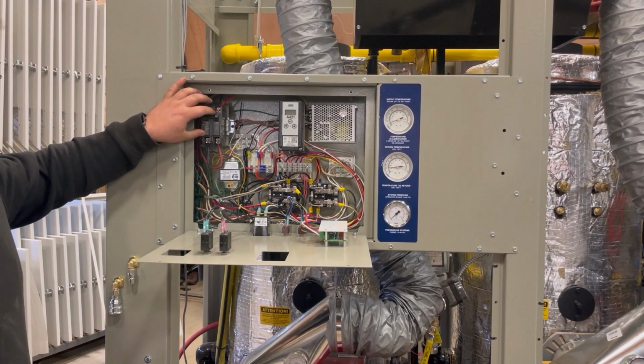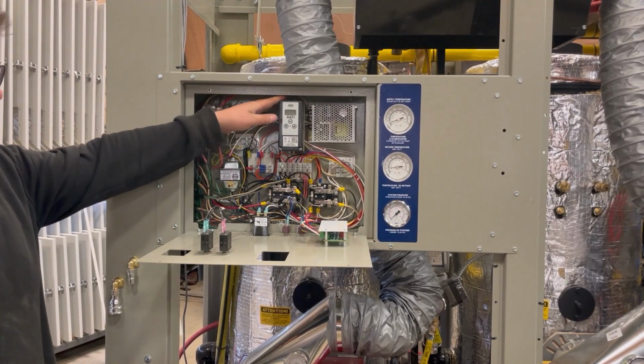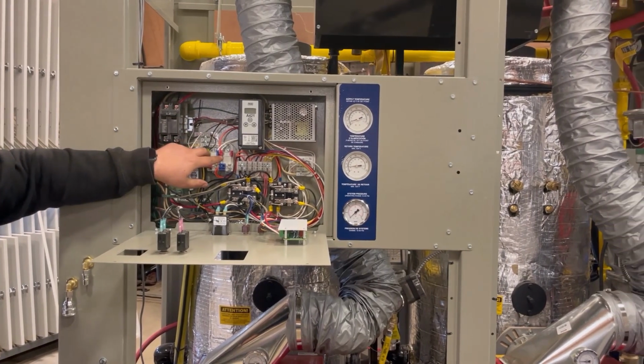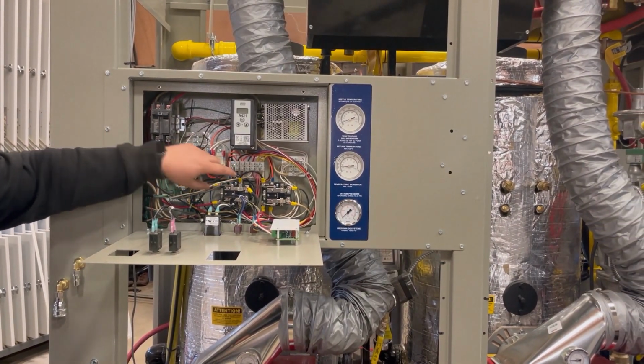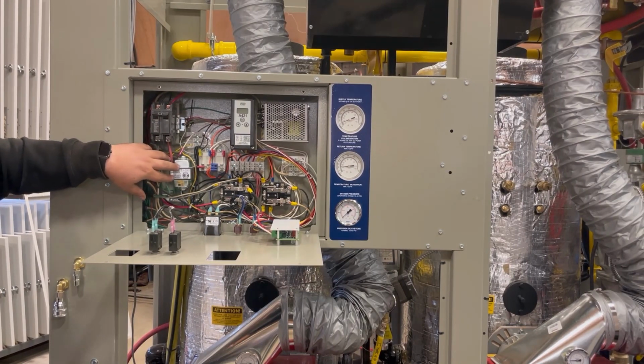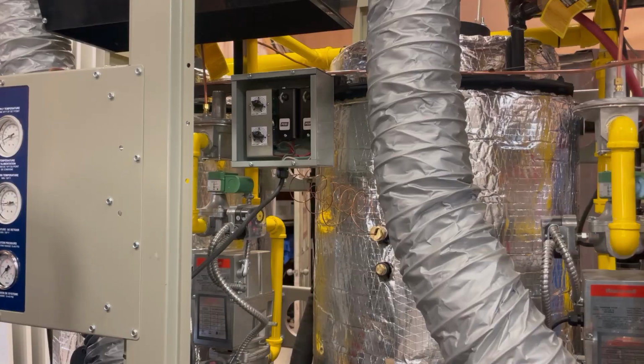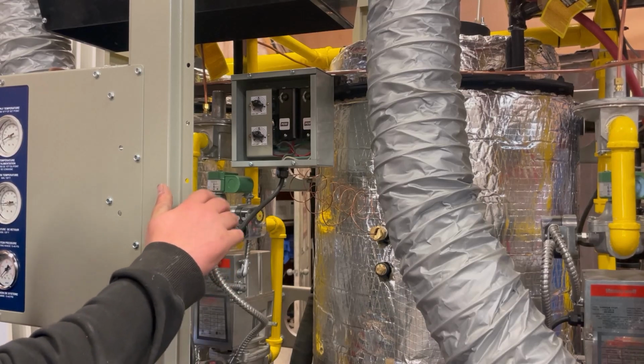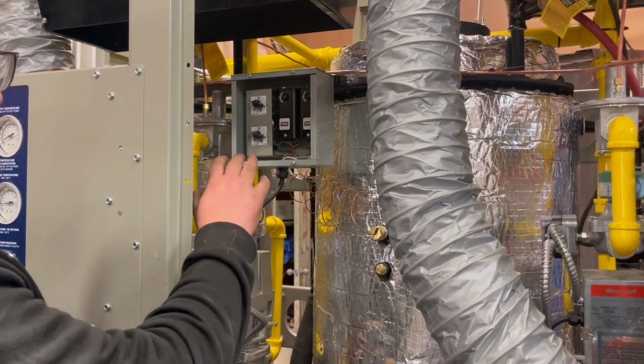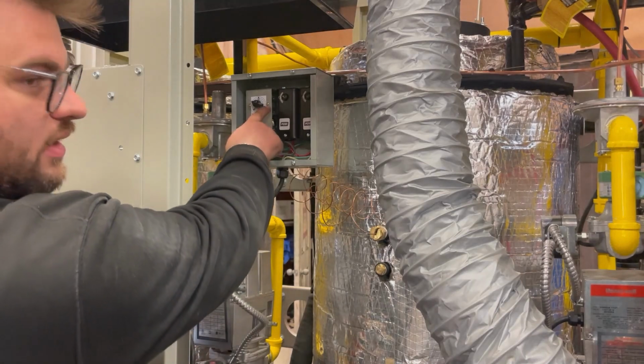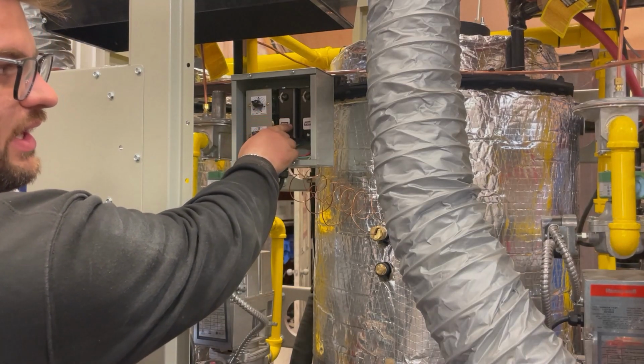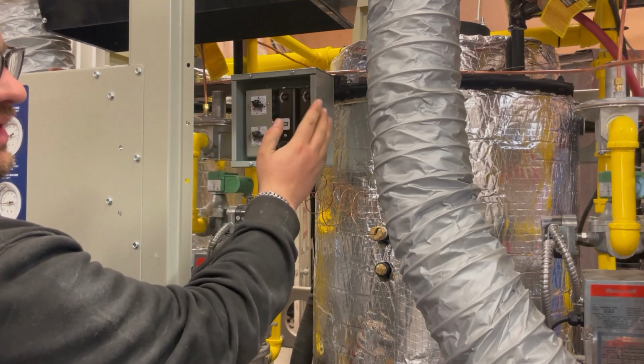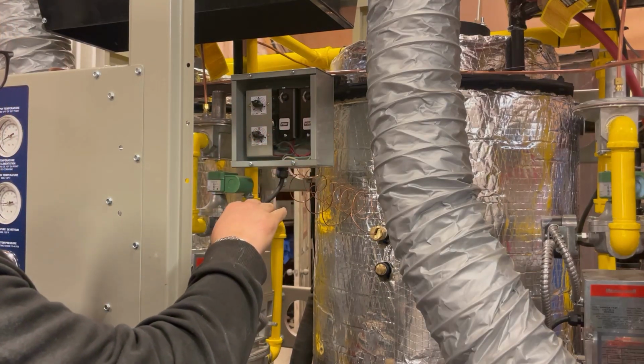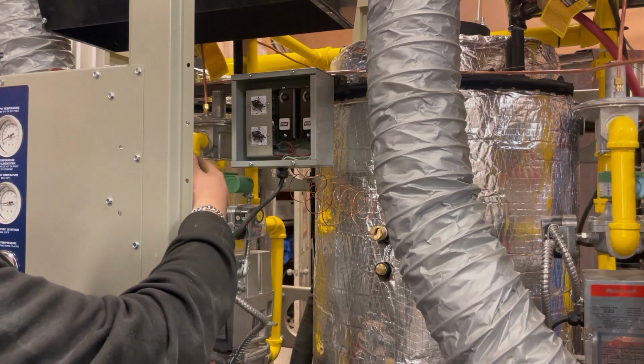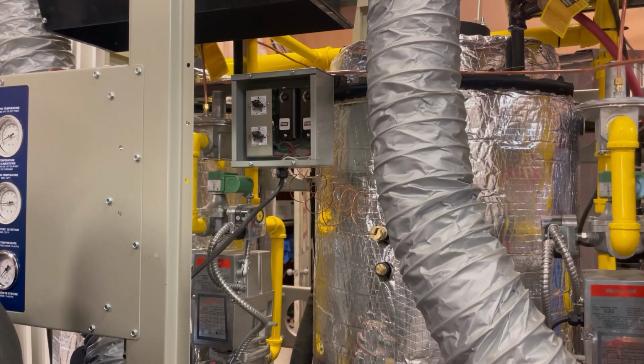Here we are inside of the control panel. We have our main breaker again and your main temperature controller. You also have 2 24 volt relays as well as 2 120 volt relays. Here's a 24 volt transformer and a 12 volt transformer. Behind the control panel, about eye level, in between both water heaters, we have our high limit switches. We have 1 automatic high limit and 1 manual high limit for each water heater, but they will each shut off the entire unit if the temperature ever gets high enough. The automatics are usually set at 200 degrees and the manual high limit is usually set at 215.